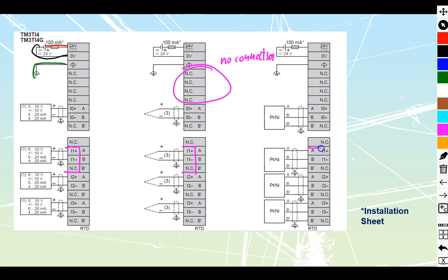But over here, where I go into my three-wire RTDs, we do need to have that reference terminal, right? We've got two of these that run the actual main data, and then one of these that's going to be a reference terminal that allows us to accurately calculate the voltage drop that's happening on that signal. So we see that over here, B and B hyphen are going to be off of there. In this case, we're ignoring that. And you'll note that even in their drawing over here, they just reverse the order so that you can see the A's and the B's when I'm using the resistive temperature devices. Okay, we're going to do just thermocouples and resistive temperature devices. We have done these in a previous video, so you can refer back to that one later on.